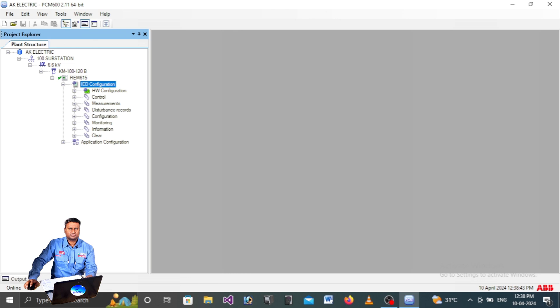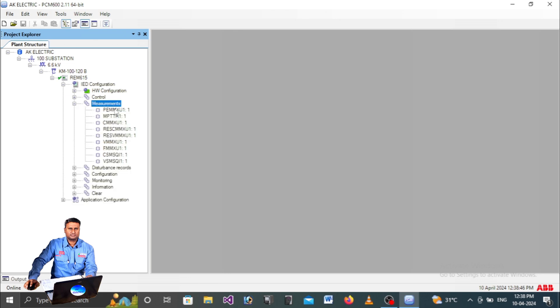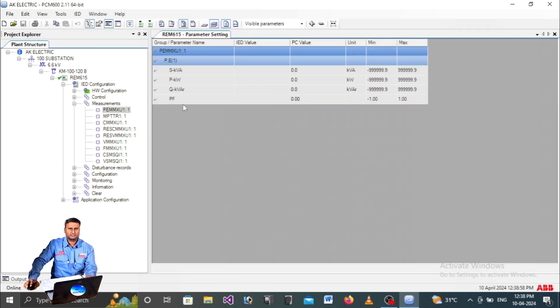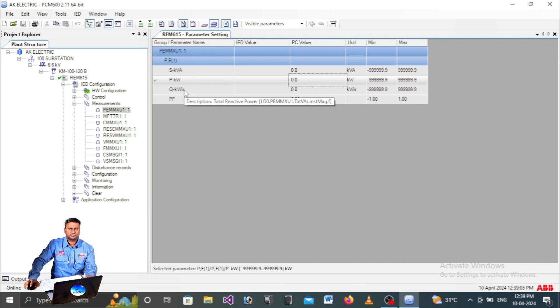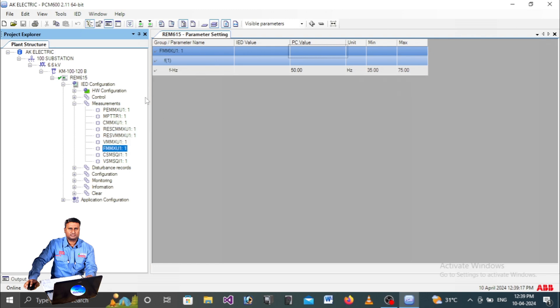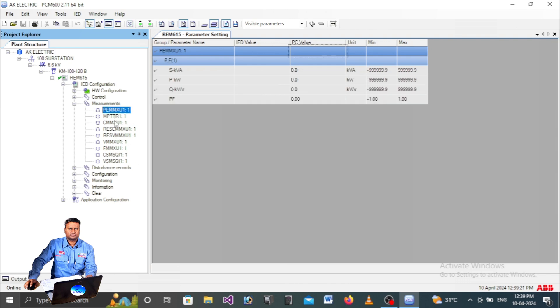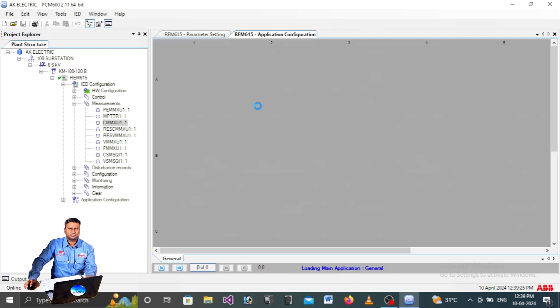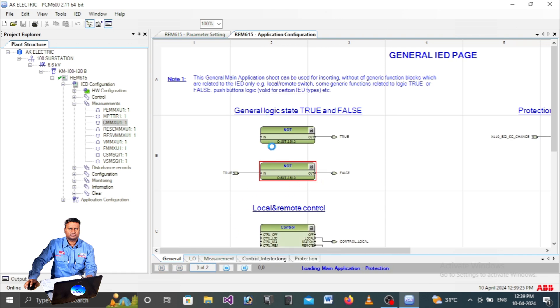Under Measurements you will find many blocks. Right-click any block and select Parameter Setting to view its details. For example, you can see reactive power, apparent power, kilowatt power, power factor, thermal level, current sources L1 L2 L3, I-naught, voltage, and frequency. Right-click any block and go to Application Configuration to see how the configuration is structured in ABB software.